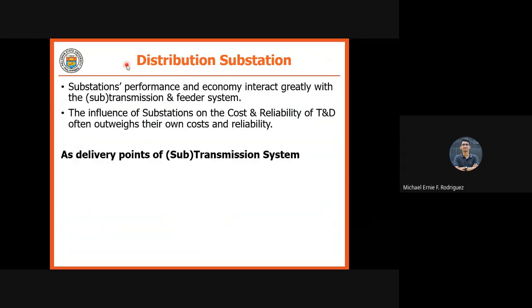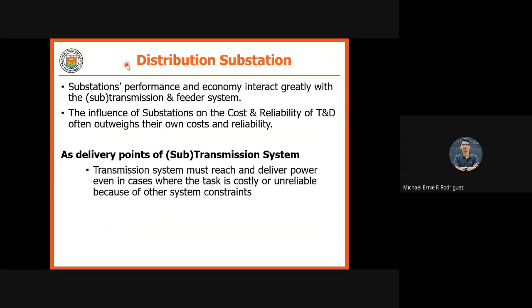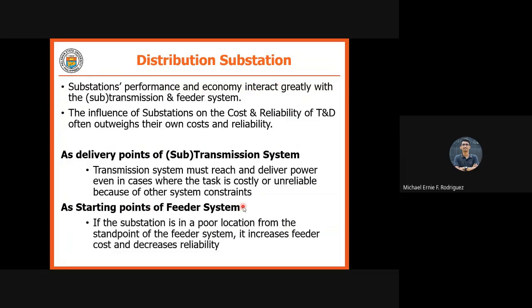So, another thing is the delivery points of the transmission system. The transmission system must reach and deliver power even in cases where the task is costly or unreliable because of other system constraints. And your distribution substation is a starting point for the feeder system. So if the substation is in a poor location from the standpoint of the feeder system, it increases feeder costs and decreases reliability. So kapag pangit yung location ng substation, makakaroon tayong problema on reliability.